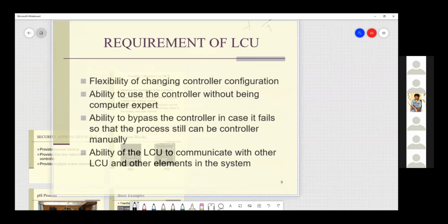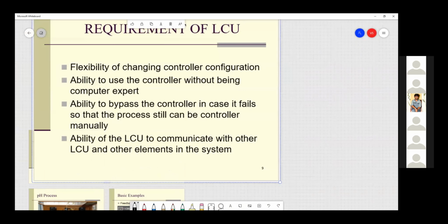The main requirement, if you want to choose one particular LCU, is flexibility of changing controller configuration. Whether you can change your Kc value, Ta value, Td value, or sometimes your optimal set point value, the inner loop configuration, or change the span of my alarm and annunciator, everything I can change.